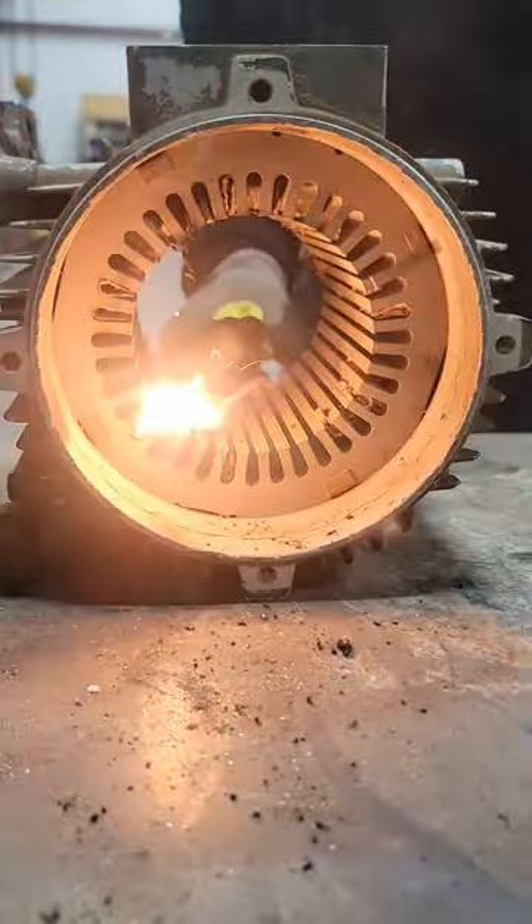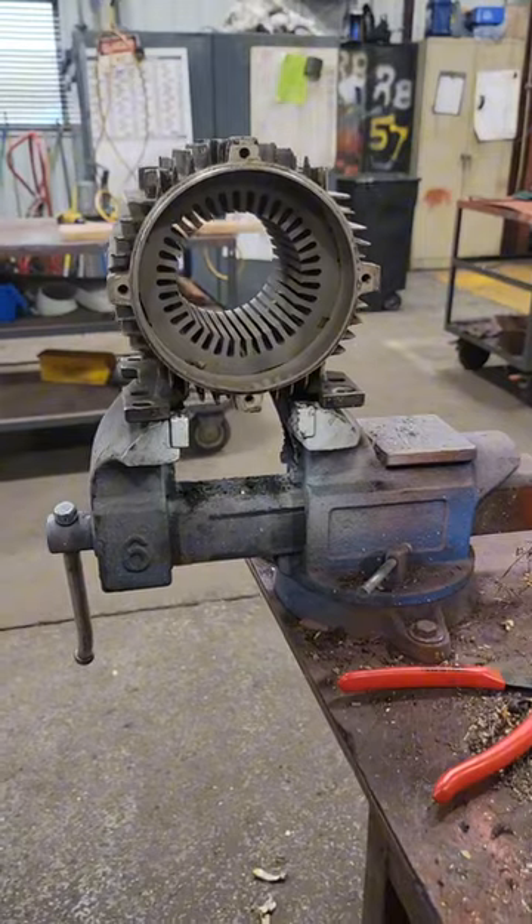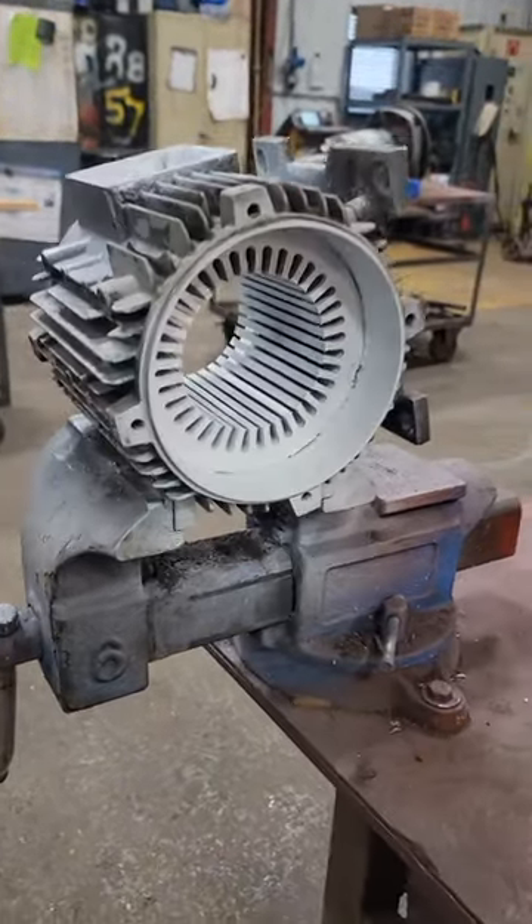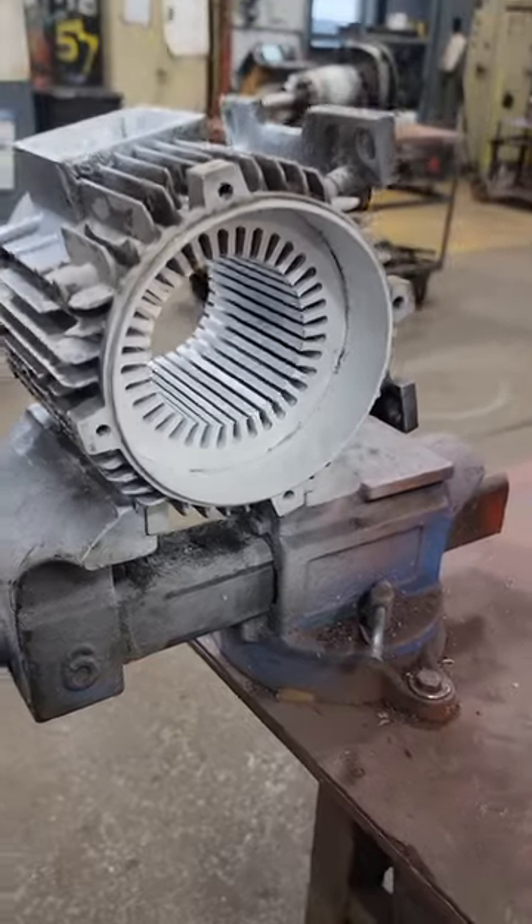Again, I'm not suggesting you do this. I'm not a fan of an open flame on these stator cores because we don't want to damage that interlaminar insulation. However, the bean counters want this bad boy back right away, so we get it all cleaned up and can start making our coils.